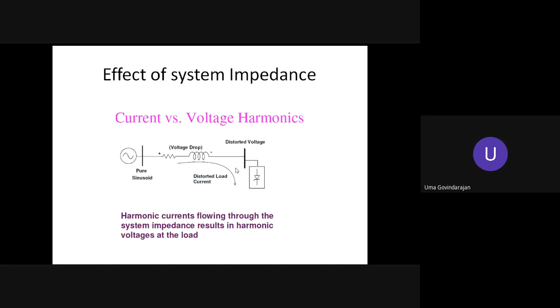Now, in this bus, many loads will be connected. If all the loads are nonlinear loads, there is no problem. In this bus, if some of them are linear load users and some are nonlinear load users, then the culprit is the nonlinear load user who is responsible for the distortion of the bus voltage. Some other linear load users may also be connected in the same bus. Even though they are genuine customers, they are not presented with a sinusoidal voltage. That is the present scenario. So the main culprit is harmonic currents flowing through the system impedance, resulting in harmonic voltages at the load. From the load end, the load voltage gets distorted and the current also gets distorted.